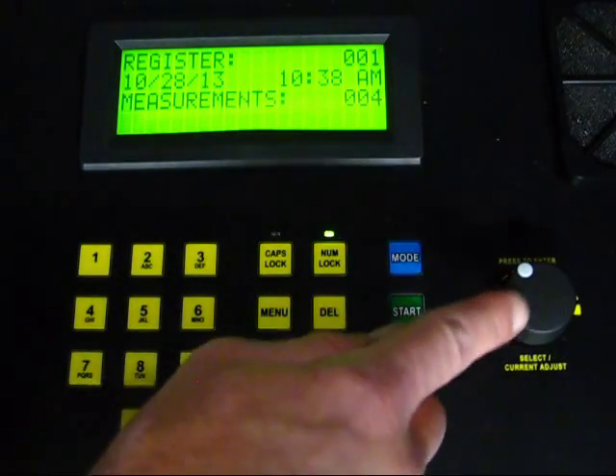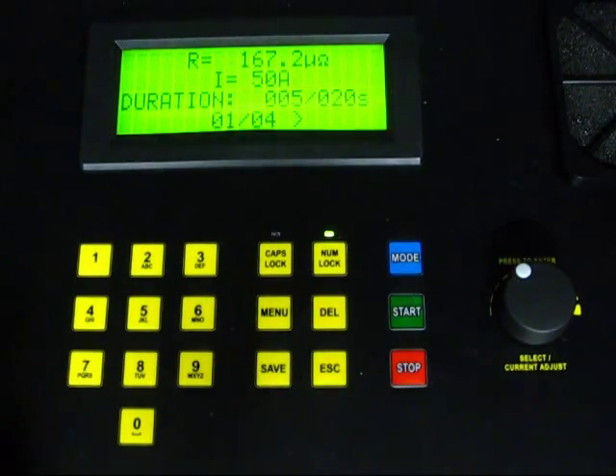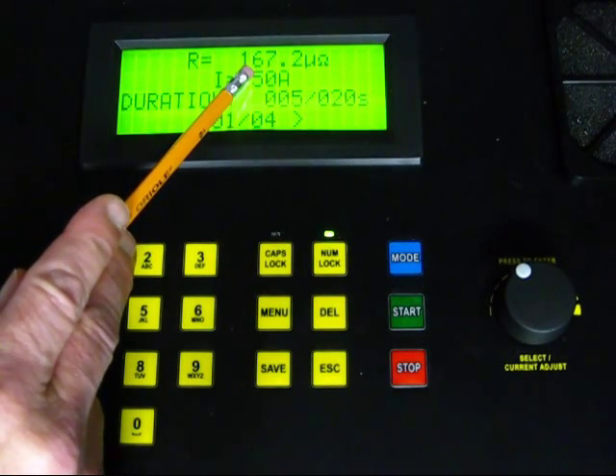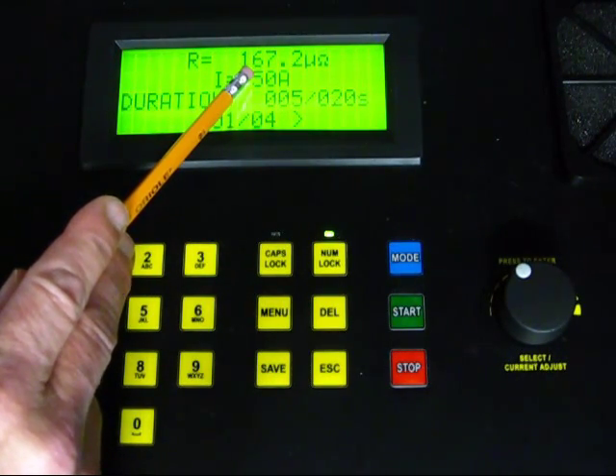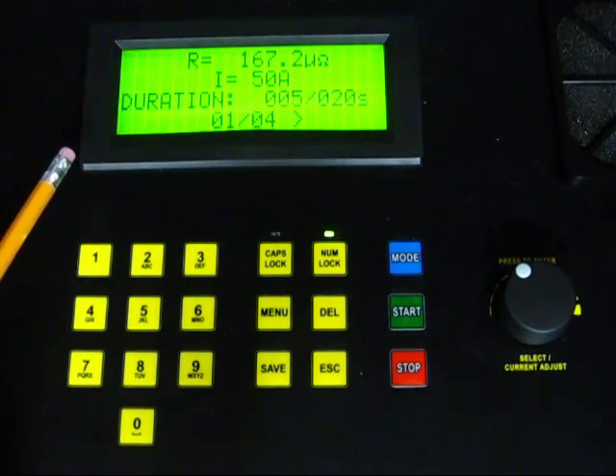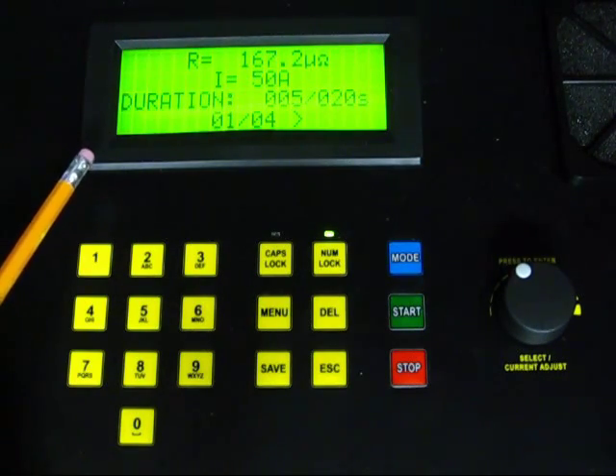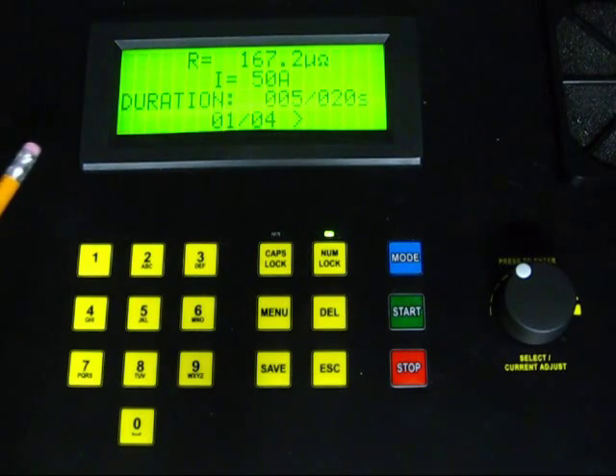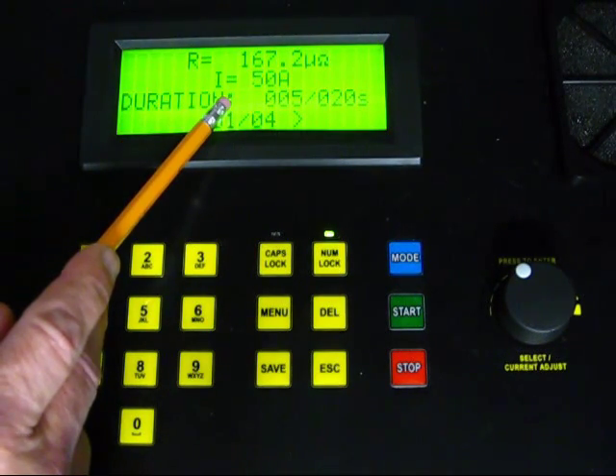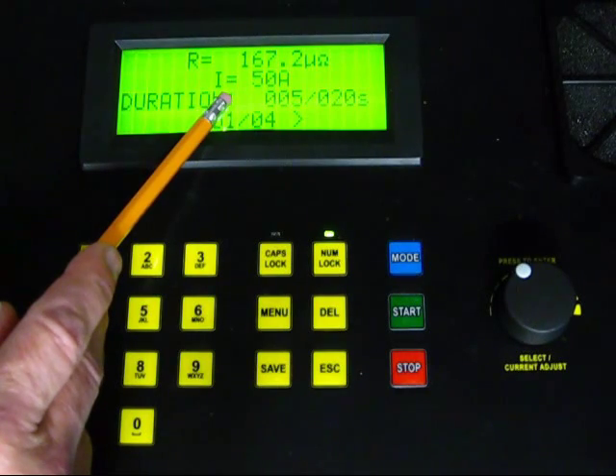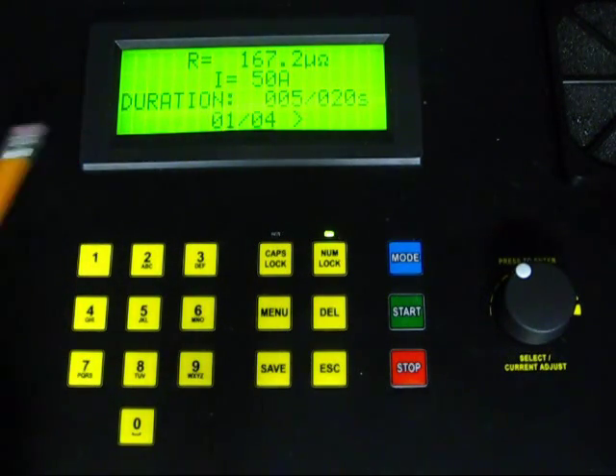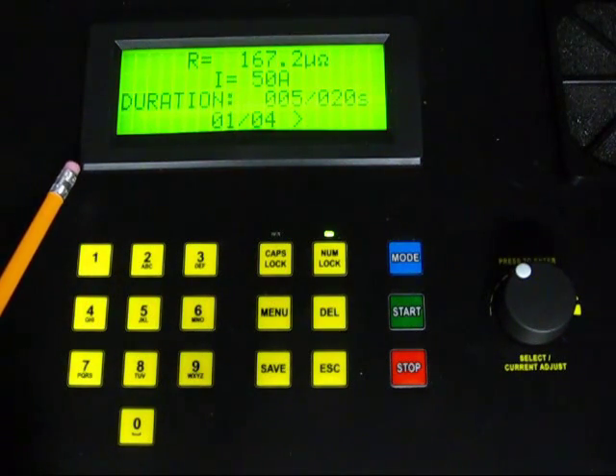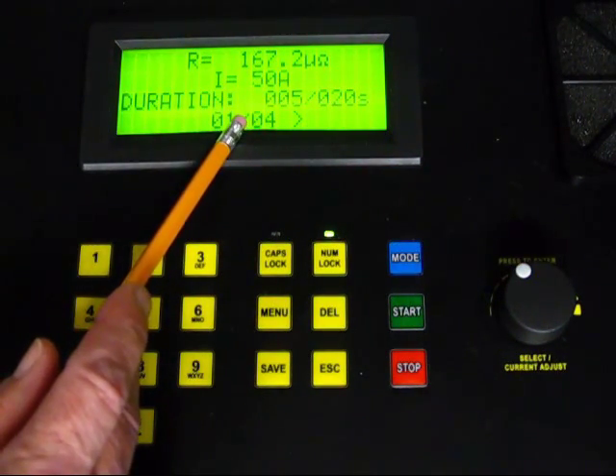Press the rotary key to view these measurements. The stored test result shows on the top line the resistance measurement at the 5 second point in the test, which in this case is 167.2 micro-ohms. The second line shows the test current, which we set earlier at 50 amps. The third line shows the test duration. Here we show the test result was obtained at the 5 second mark within a 20 second test. The bottom line will show that this is the first of four measurements stored within this test.